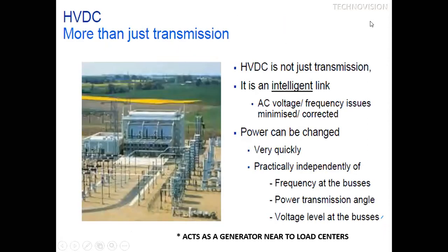So HVDC is not just a transmission. We know that today is the era of artificial intelligence, so everything can be done with the help of intelligent controllers, and you will have fine control over any system. In power systems also, in recent technology, the HVDC link acts as an intelligent link. You can correct any voltage and frequency, and minimize whatever changes there are. You can change power very quickly and easily. It is independent of the frequency at the buses, the power transmission angle, and the voltage level at the buses. And the biggest advantage of HVDC is that it acts as a generator near the load center. That is the biggest benefit of the HVDC link.